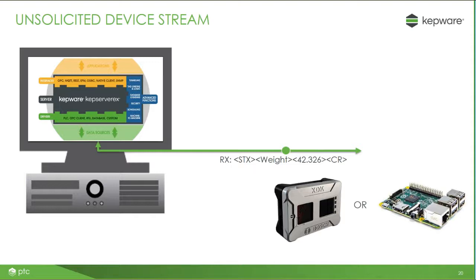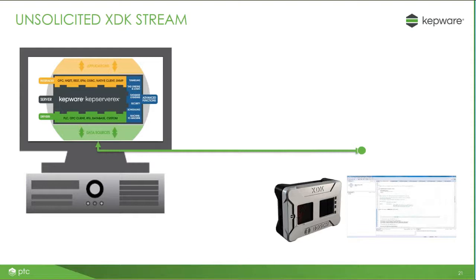Another way to interact with a device is to configure it to send an unsolicited message on a certain interval. In the example here, a message is streaming to KepServer on an interval of two seconds. Within that message you have a start-of-message ASCII character, followed by a weight command, and then the weight value. KepServer is just sitting back, opening up a UDP port to listen for that message. In fact, that's exactly what we're going to demonstrate today — we are working with a Bosch XDK device, which is going to stream a UDP message to KepServer. That message is totally configurable by the user, so you have control to program the message being sent, and also to program KepServer to understand that message.